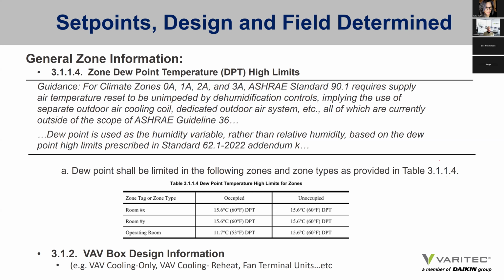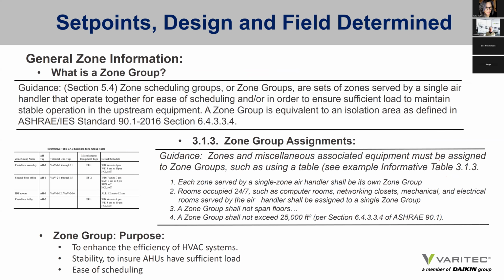The general zone information then goes on to VAV box design information, and it talks about VAV cooling only, VAV cooling with reheat, fan terminal units such as parallel boxes, series terminal boxes, etc. We just don't have time to go into those today at all. It also goes on to define what a zone group is that I've already referred to earlier in today's presentation. Zone scheduling groups, or zone groups, are sets of zones served by a single air handler that operate together for ease of scheduling and/or in order to ensure sufficient load to maintain stable operation in the upstream system. It's not uncommon, especially for DX units, to struggle when there's low load. And so this language helps to overcome that challenge by making sure that at minimum load, there's adequate load to keep a DX unit online.